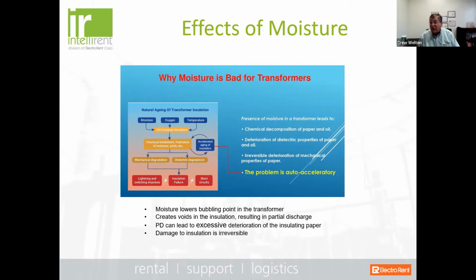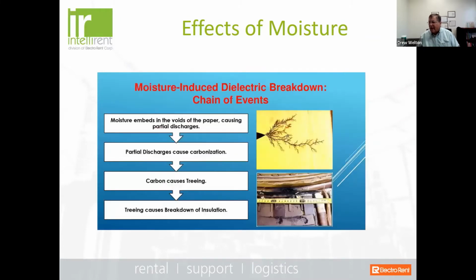Now, the partial discharge can actually lead to excessive deterioration of the insulating paper and damage to the insulation, which, unfortunately, once it gets to a certain point, is irreversible. There's really nothing you can do about it. So it's autoacceleratory. That means that the worse it gets, the more moisture it starts to create. So the point I'd like to make here is that the sooner you address moisture issues in the transformer, the more chances you have for better life extension of that asset.